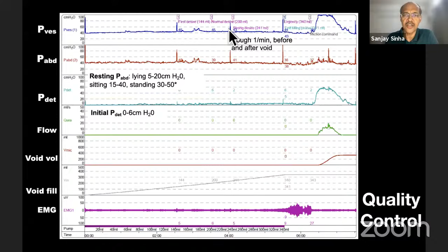The initial PDET could be somewhere between 0 and 6. You would ordinarily expect it to be 0, but it's not always precisely 0. And you ask the patient to cough typically once a minute because you want to see whether the transducers are working well. And if they're working well, you should see a good subtraction of the cough spike. So the cough spike pressure is transmitted both to the bladder as well as through the abdomen. And they should subtract out because that's not contributed by the detrusor muscle. So you should find that on the PDET channel, there is very minimal or a little spike or a biphasic kind of spike. The fine trace should match. So this is a good method to look for quality control.